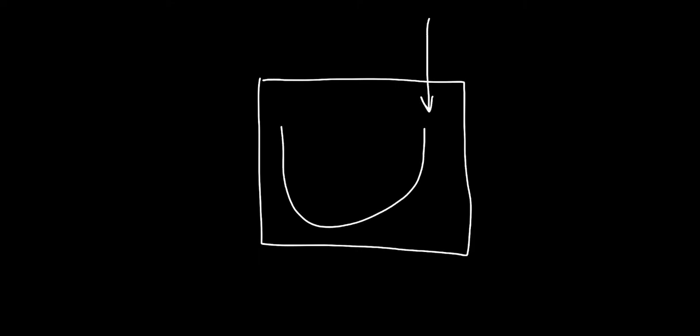The second way to control particle migration is clean air changes. By introducing clean air and exhausting room air, the particle counts are able to be controlled, preventing migration as a result of a difference in concentration.